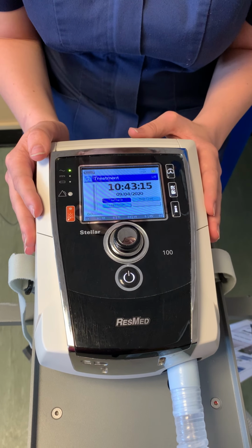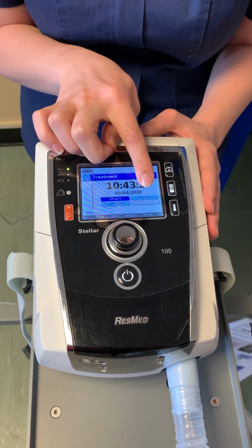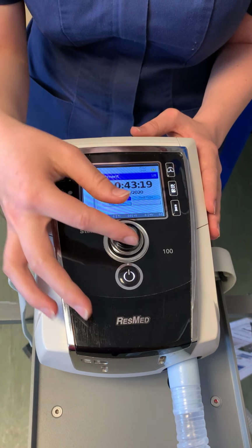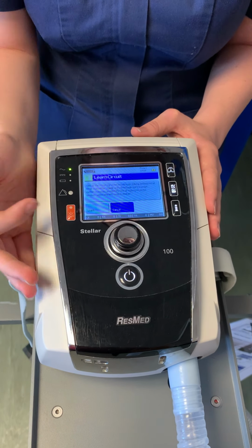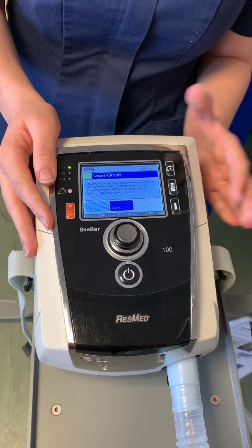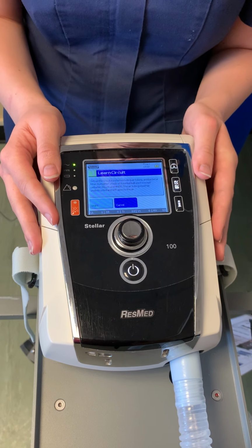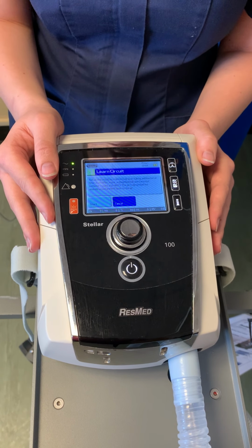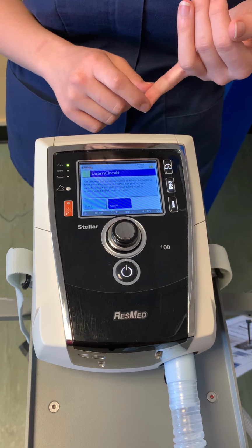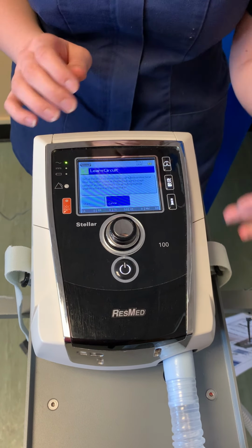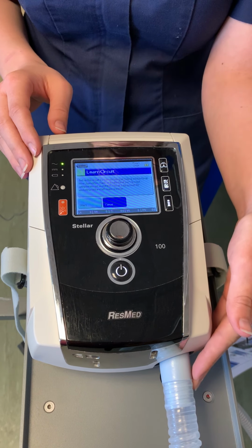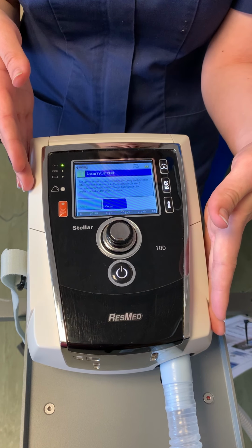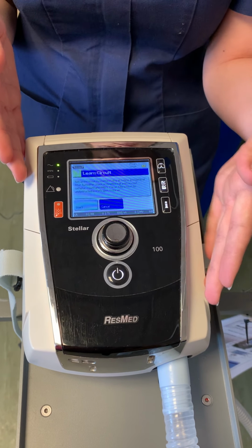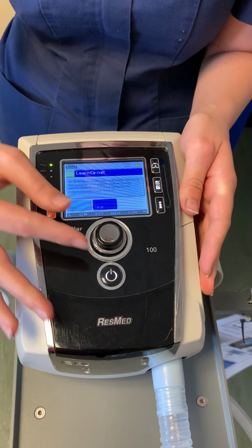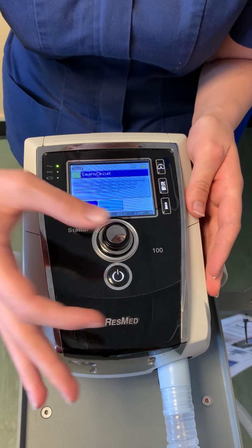So when you come to the home page, you have a ramp, a face mask and a learn circuit. The most important thing to do first is your learn circuit. Your equipment needs to be set up with the face mask and the HME filter, because the learn circuit not only tests if it's safe to use, it also checks for the dead space. Then you know that the observations you're getting are just from the patient and nothing to do with the ventilation tubing. So all you have to press is start.